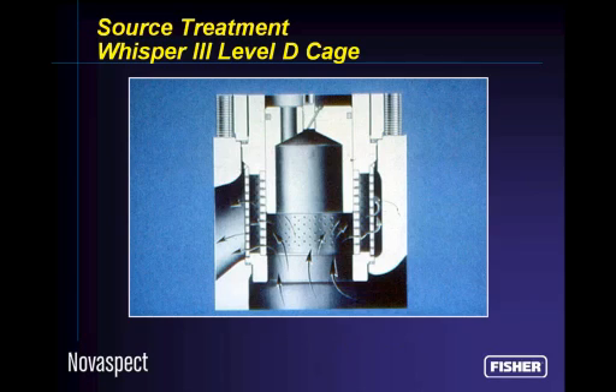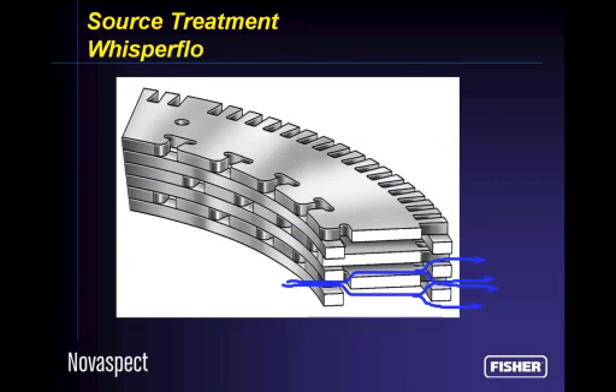Anytime we have to put an elaborate trim in a valve to reduce noise, it essentially is going to have the same characteristic. It's going to break the flow stream up into a whole bunch of independent flow streams that we hope don't interact. When you get these flow streams interacting, these jets, we end up with supersonic shock cells, and we get a lot of noise. So this has to be carefully done, and the spacing of the holes and the size of the holes are engineered based on the differential pressure across the valve. And these noise attenuating trims take different forms and different levels of cost, but the point is they all essentially break up the flow stream into a whole bunch of flow streams.